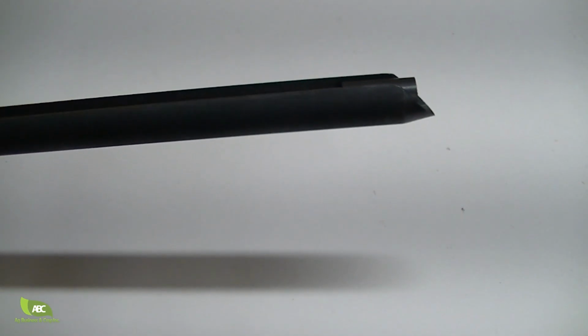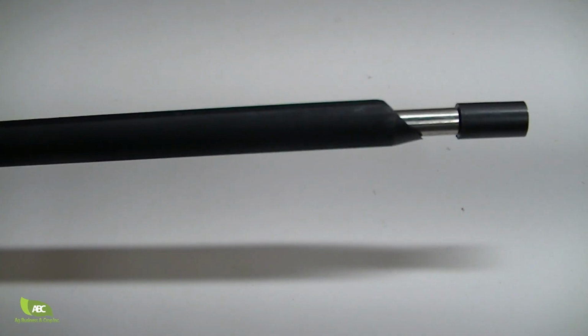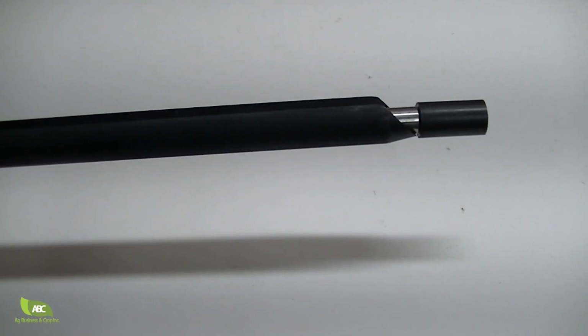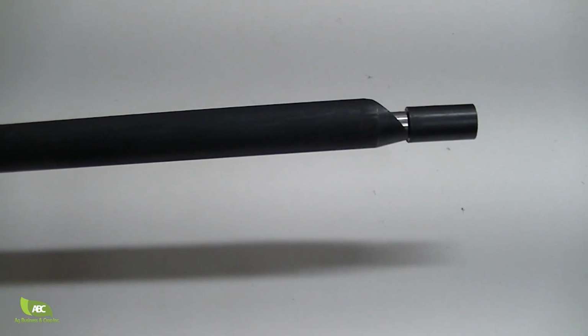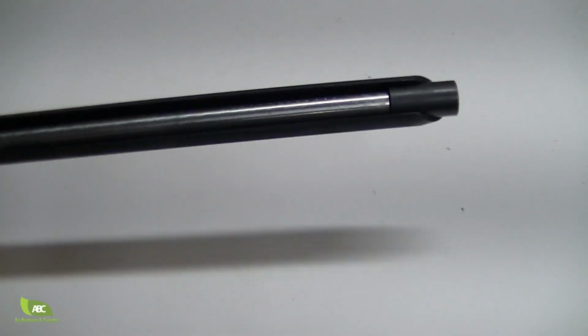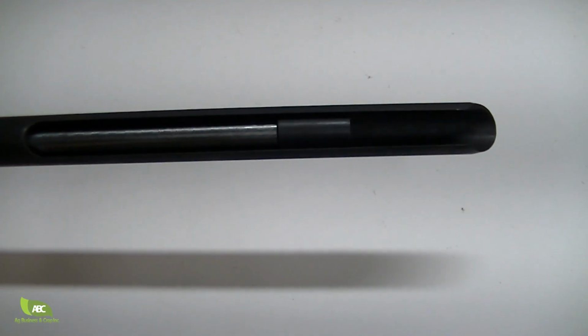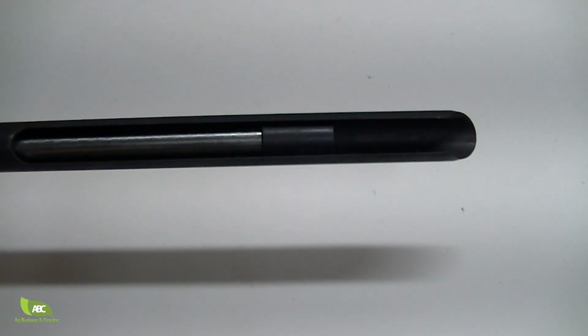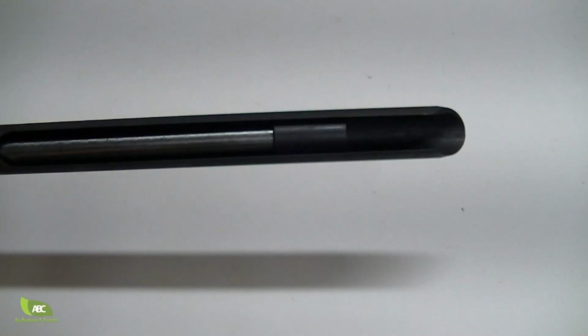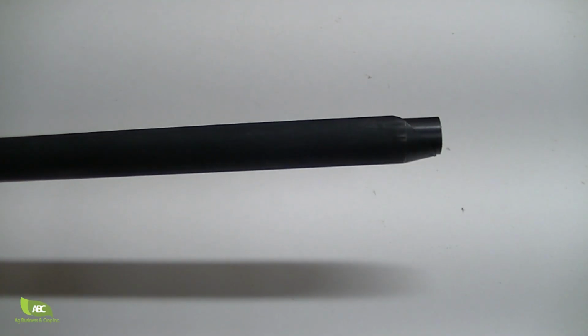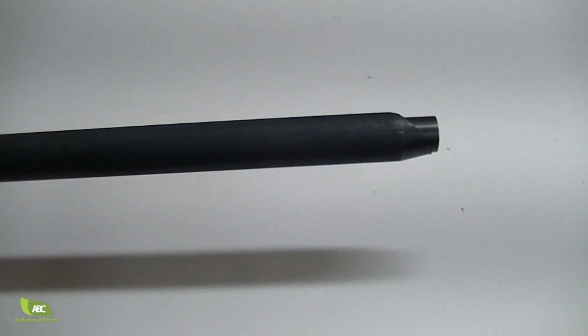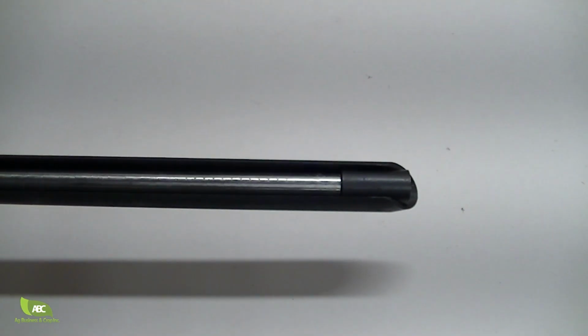So after replacing your probe, you need to pay attention to the ejector tip. It shouldn't be sticking too far out, or when it's coming up, it has the risk of hitting the tip of the probe, causing damage. You also don't want it too far in, otherwise it wouldn't eject the whole sample in the soil box. You want the ejector tip sticking out at least 1 to 2 millimeters of the probe tip. More than that or less than that can cause problems.